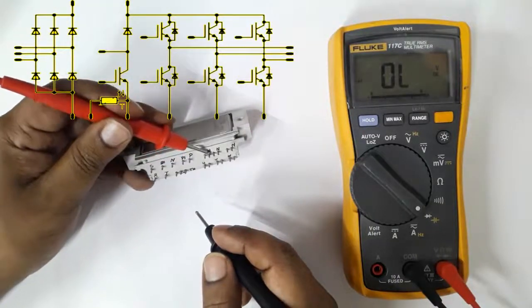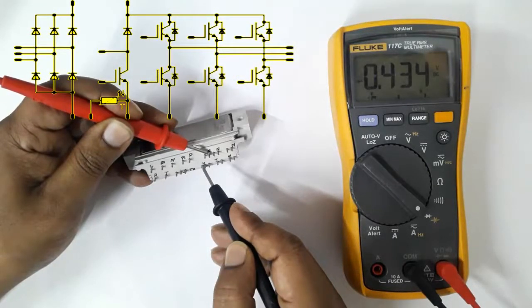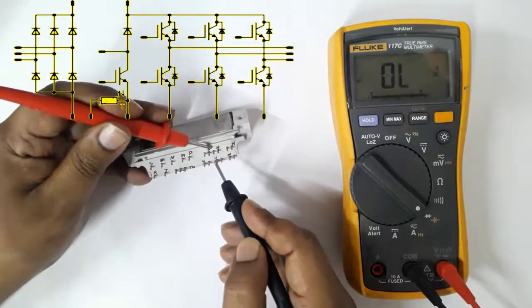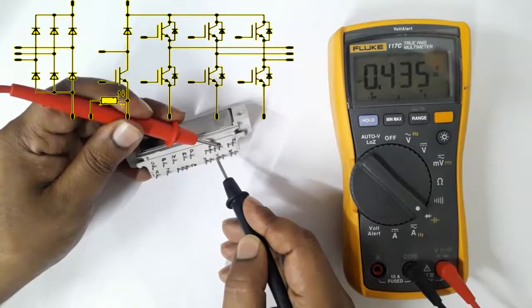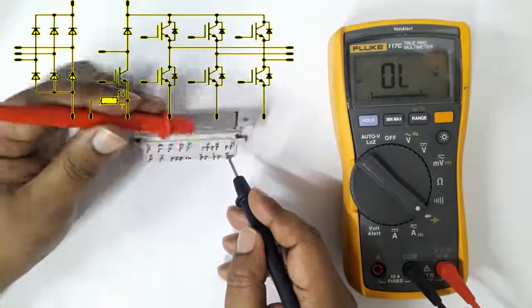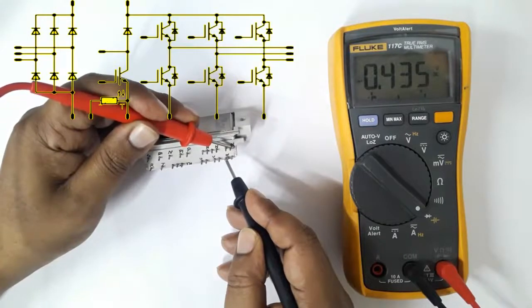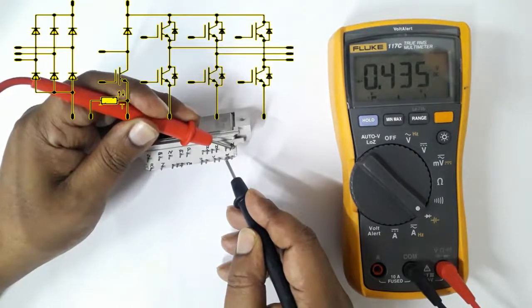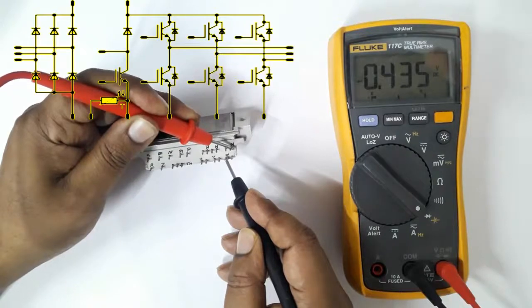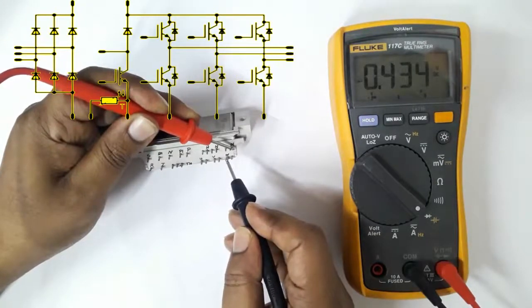Now testing against the negative terminal. Set the red probe in the negative terminal and by black probe check U — about 0.4 volt DC. For V, negative terminal is also about 0.4 volt DC. For W terminal, negative terminal is also about 0.4 volt DC. U, V, and W — all three terminals against negative terminal are identical. For all negative terminals we use the red probe, and the black probe is used for output terminals U, V, W — all about 0.4 volt DC.